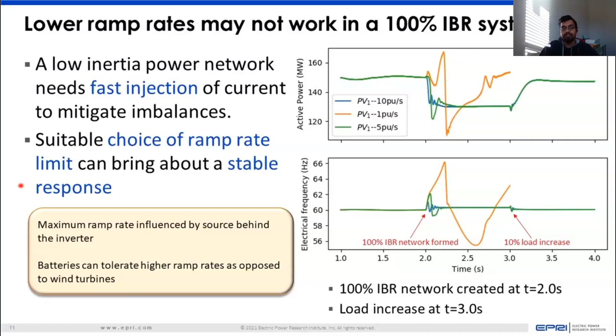So if we go back to that same network where we created the 100% inverter-based scenario, and you have to go down to a 2 per unit per second ramp rate, then in this case we needed 3 plants of 100 MVA each, rather than having the 2 plants of 200 MVA each for the 5 per unit per second scenario. So the lower the ramp rate constraint the resources are subject to, the more resources one will need to provide this kind of frequency response service in a 100% inverter-based scenario.